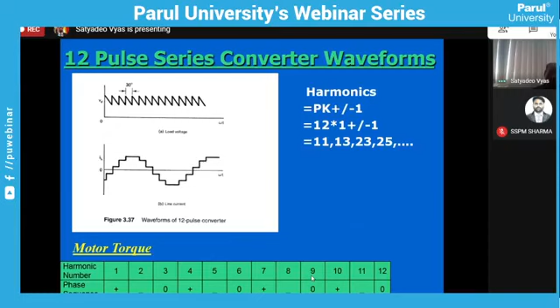In case you are not using a VFD, you are simply running the motor with a star delta starter, and after completion of the delta timing, it is running at full speed. Even in this case, if one lead of the rotor gets open, what will happen? The motor will draw unbalanced current. Unbalanced current can be resolved into two components: one is positive sequence, one is negative sequence. That negative sequence component will reduce the positive sequence component torque, and thus the net torque will decrease. That's why the motor will draw more current.